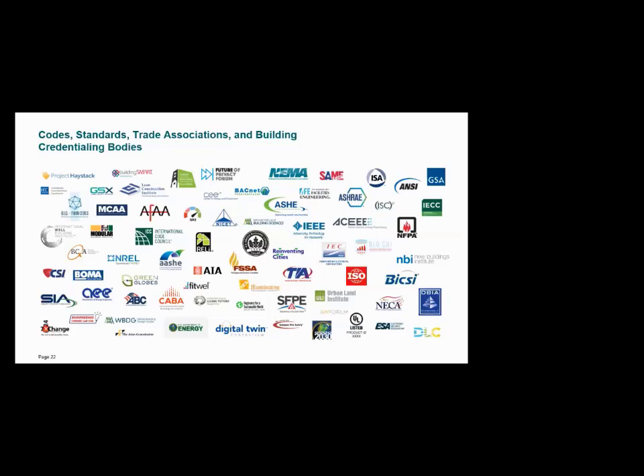There are a couple of standards out there that are worth looking at when it comes to smart buildings. ASHRAE 90.1 is an energy standard for buildings that would be worth looking at. Guideline 36 gives you your high performance sequences of operation.